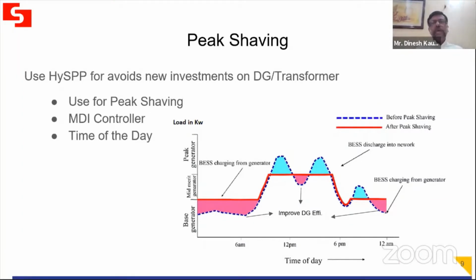Another reason for installing these hybrid solar power plants is peak shaving. There are a lot of graphs and technical details, but essentially, if you have a 50 kilowatt load that sometimes during the day goes up to 60 kilowatts, what would you have to do? Buy a new DG, install a bigger transformer? No, don't do that, don't invest more money there. Invest in a hybrid solar power plant instead. The extra 10 kilowatts your load demands for a short period will come easily from your battery for that time. That is peak shaving. As demonstrated in the center, when the peak load occurs, it comes not from your generator or bigger transformer, but from the battery. No new investments needed, that is the beauty of peak shaving.